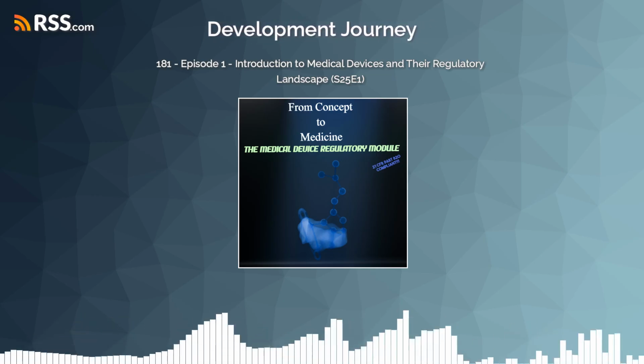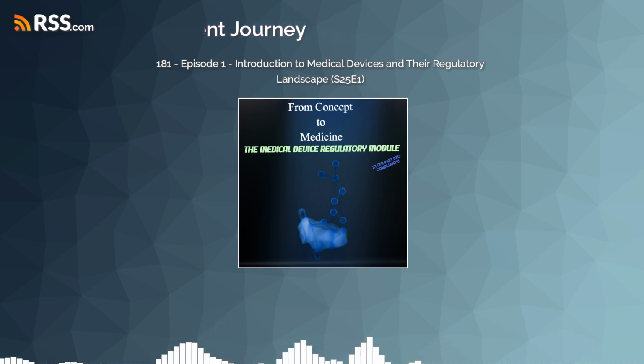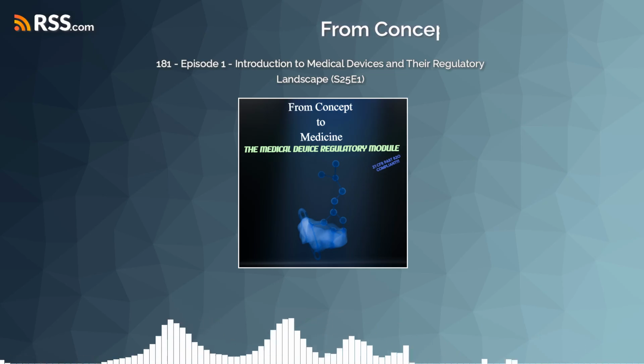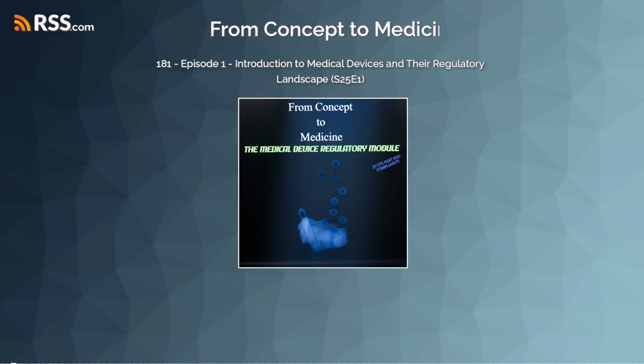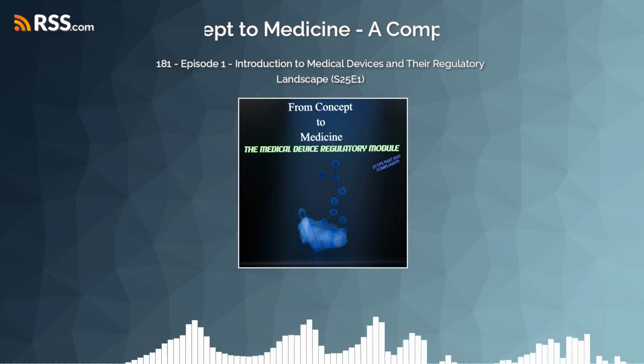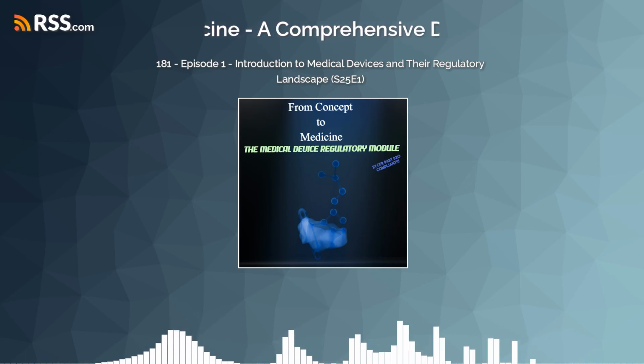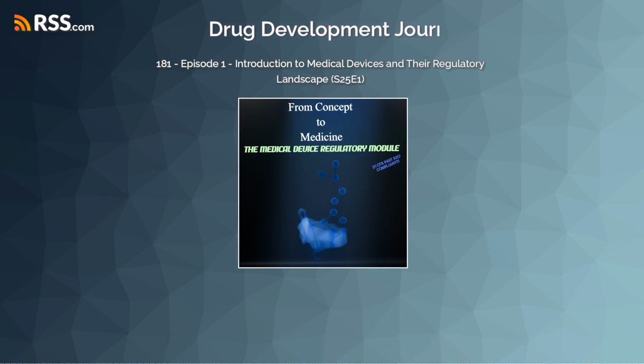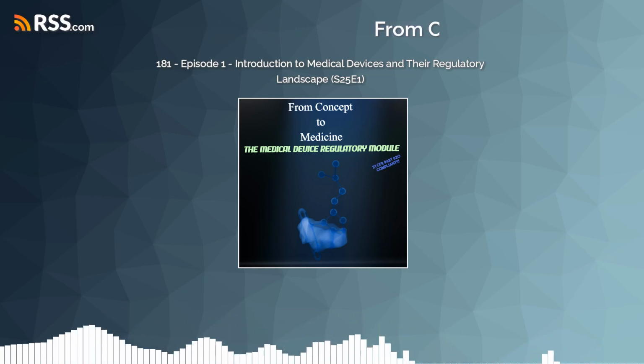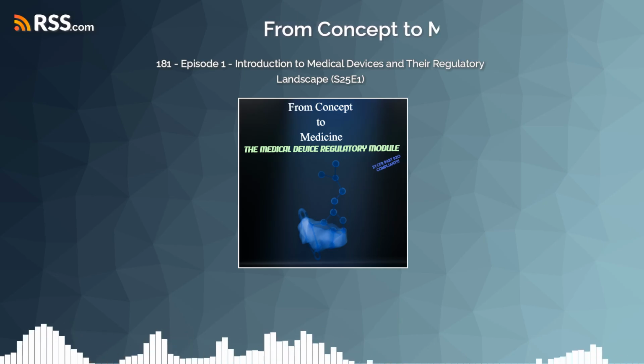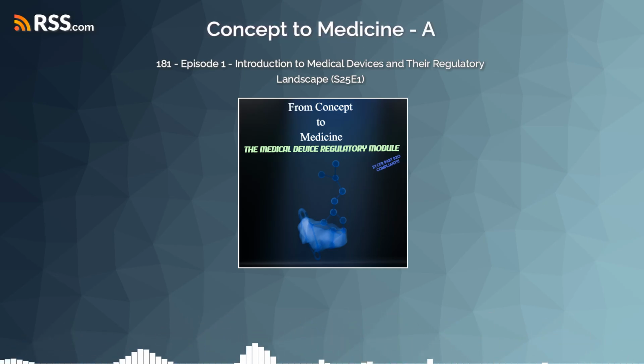Four classes: I, IIa, IIb, III. Right, and the specific classification rules can differ. For example, under EU MDR, many devices previously in lower classes got up-classified. And something like a sterile Class I device in Europe often requires notified body involvement for the sterility aspects, making its pathway look a bit more like a Class 2 device pathway in the US context. So you can't just assume your FDA class translates directly. You really have to assess classifications separately for each region. Absolutely critical for a global launch strategy.